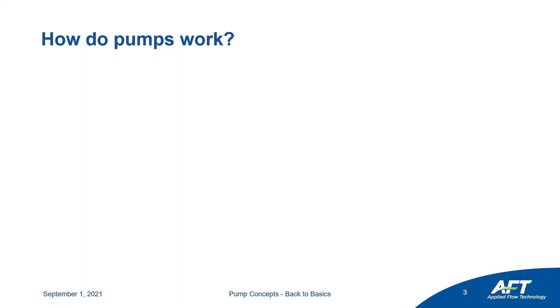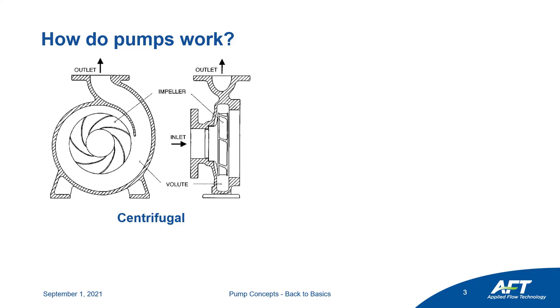First question: how do pumps work? There are really two big categories — centrifugal pumps and positive displacement pumps. We'll focus on centrifugal pumps since those are the majority of pumps you're going to be considering. A centrifugal pump works by having flow come in and hit the eye of the impeller. The impeller is spinning at a rapid rate, which imparts momentum onto the fluid. By accelerating that fluid, it's adding energy. All of that momentum is carried until it hits the wall, where the kinetic energy is converted into pressure, and that high pressure is what drives flow ultimately.